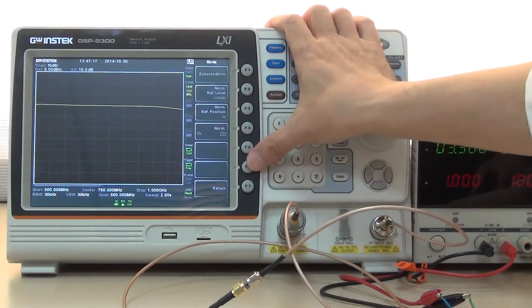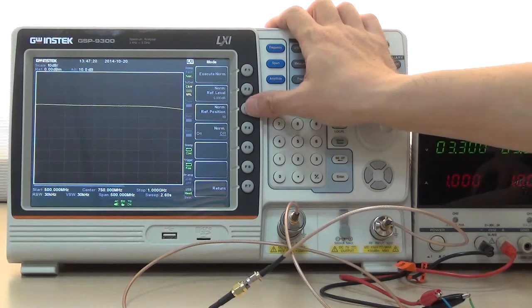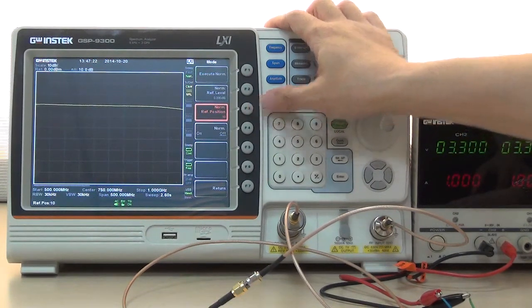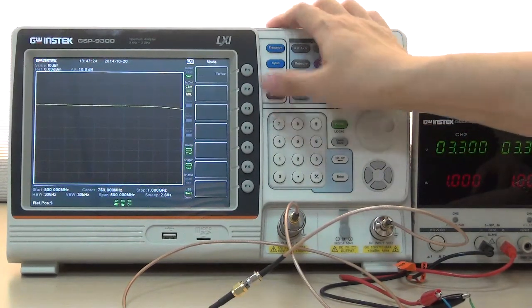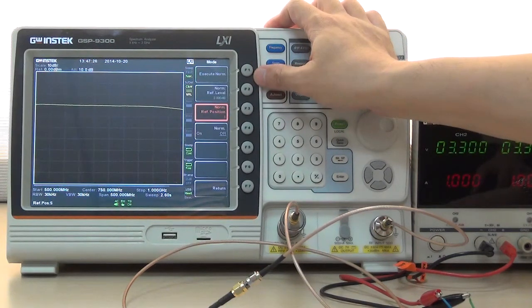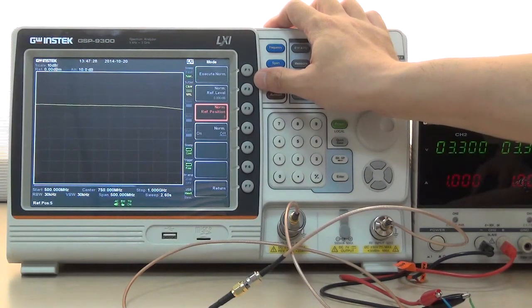Next, press F6 Normalize and F3 Reference Position and input 5 to set Reference Position at the center of Division 5.